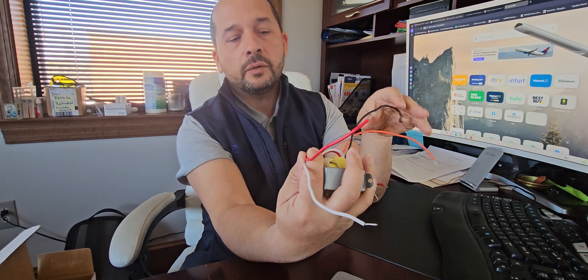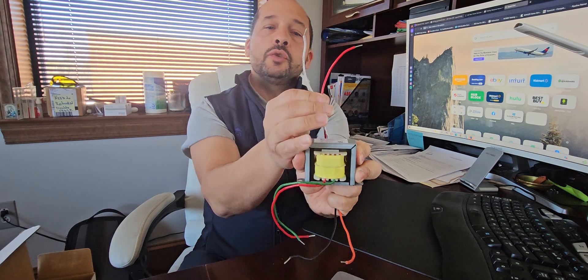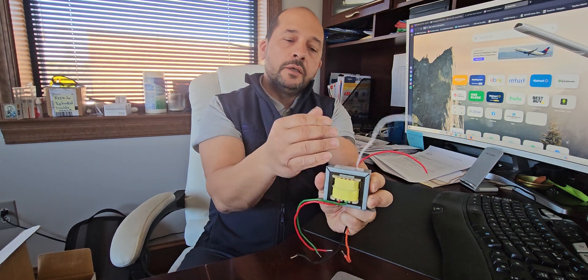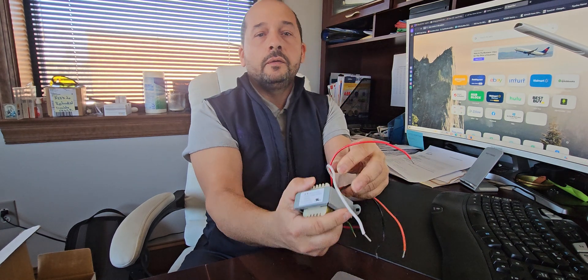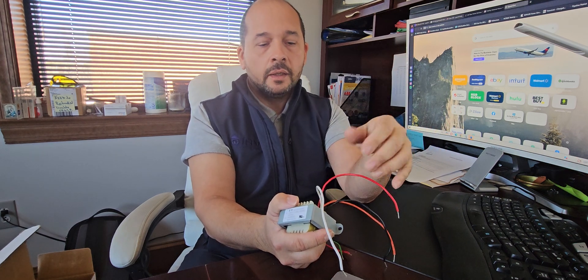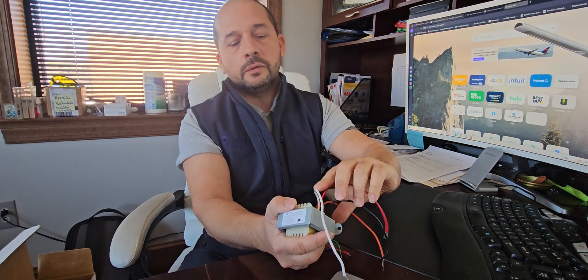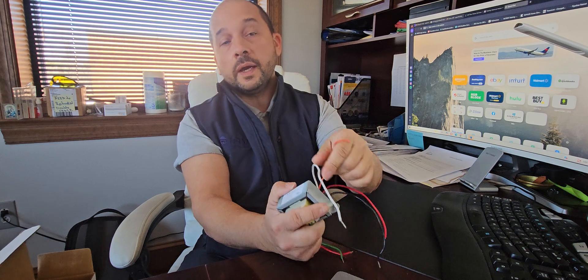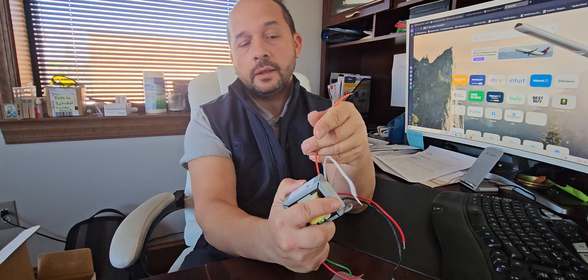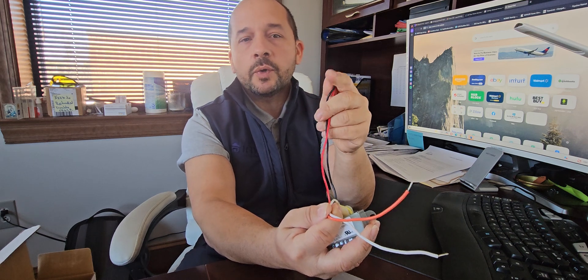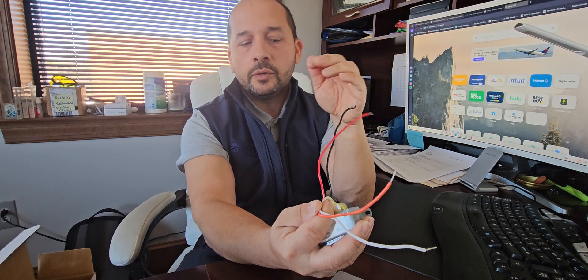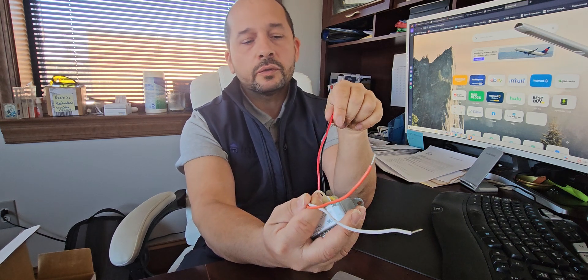For 240 volts, let's say you have a heat pump and the transformer is bad. You're going to use white again and orange. That's your 240 volts right here. Make sure those ones are capped off—you're not going to use red and black in that application.